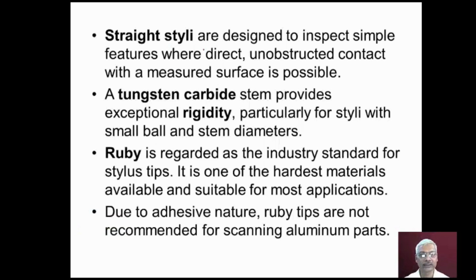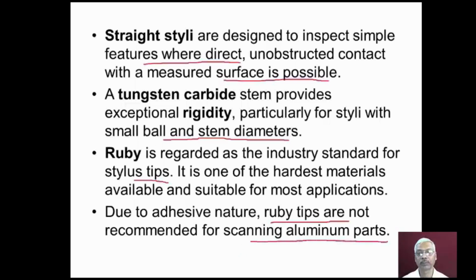Now, straight styli are designed to inspect simple features where direct, unobstructed contact with a measured surface is possible. A tungsten carbide stem provides exceptional rigidity, particularly for styli with small ball and stem diameters. Ruby is regarded as the industry standard for stylus tips. It is one of the hardest materials available, and it is suitable for most applications. Due to its adhesive nature, ruby tips are not recommended for scanning aluminium parts.